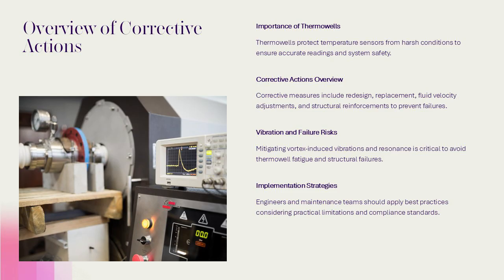Thermowells are critical components in process systems, designed to protect temperature sensors from harsh operating conditions. When a thermowell exhibits a likelihood of failure, LOF, equal to 1, corrective actions become essential to ensure operational safety and reliability. This presentation focuses on design solutions, best practices, and remedial measures outlined in Technical Module T12. The primary goal is to mitigate risks associated with vortex-induced vibrations and structural failures.